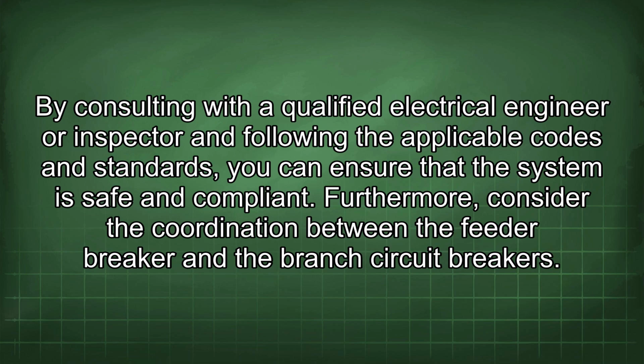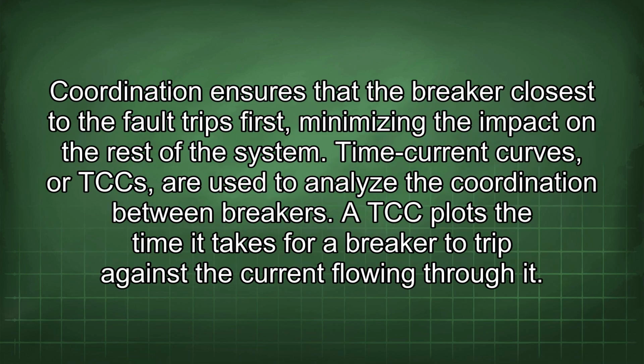Furthermore, consider the coordination between the feeder breaker and the branch circuit breakers. Coordination ensures that the breaker closest to the fault trips first, minimizing the impact on the rest of the system. Time current curves, or TCCs, are used to analyze the coordination between breakers. A TCC plots the time it takes for a breaker to trip against the current flowing through it.